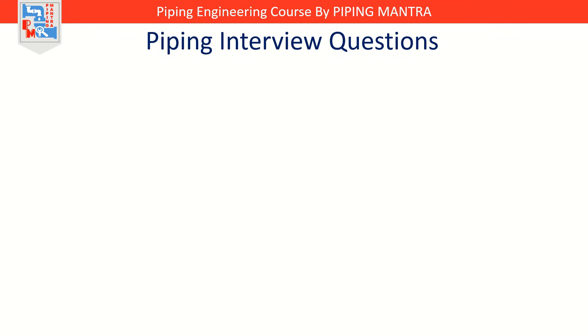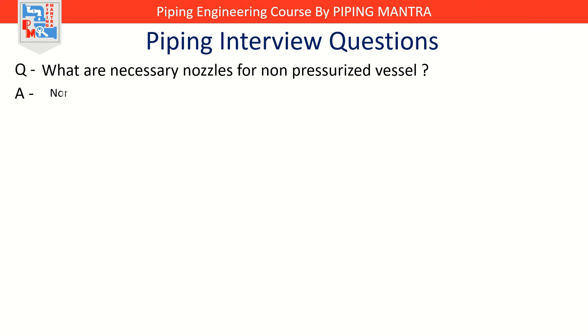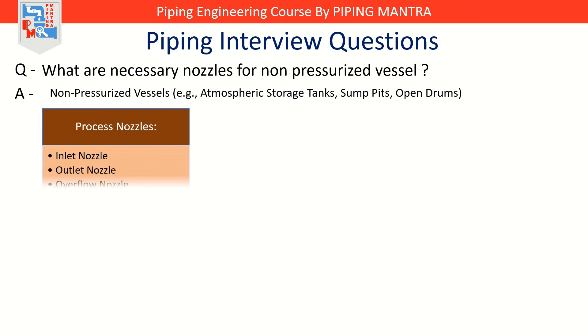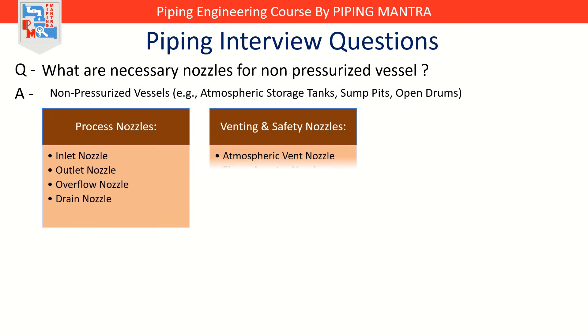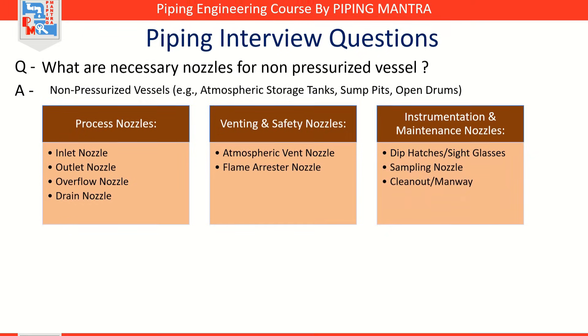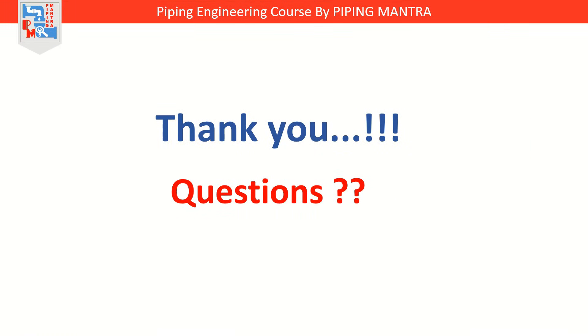Not all vessels are pressurized, so let's also look at the nozzles for atmospheric or non-pressurized vessels. What are the necessary nozzles for non-pressurized vessels? These include tanks, sumps, or open drums. Process nozzles are: inlet nozzle for filling, outlet nozzles for liquid extraction, overflow nozzle to prevent overfilling, and drain nozzle for complete emptying. Venting and safety nozzles are: atmospheric vent nozzle — it lets the tank breathe — and flame arrestor nozzle for fire protection in hydrocarbon service. Instrumentation and maintenance nozzles include: dip hatches or sight glasses for manual checks, sampling nozzle for quality testing, and clean-out or manway for sludge removal and inspection.